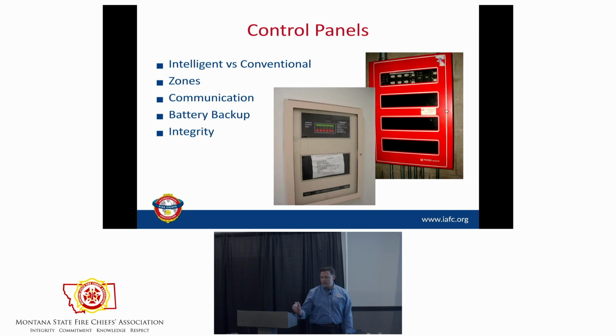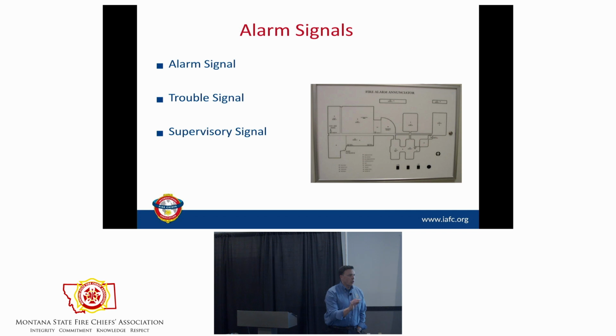One of the weirdest nuances with fire alarm systems, in storage occupancies, get a load of this. I can build a 1 million square foot storage occupancy. 1 million square feet, big building. I can build that building and not put one notification device inside the building. Not one, and it meets code. It's the weirdest thing. So your crews can respond to a water flow alarm because it's still required to have an alarm. It's still required to monitor the sprinkler system, but notification is not necessarily required. It's the weirdest thing when your companies respond and nobody's evacuated the building, and they're like, hey, what's up? Why are you guys here? It's quite possible they don't know. And so know the limitations on the various systems.